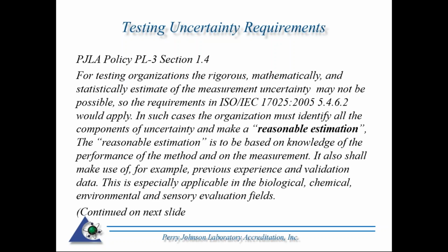In such cases, the organization must identify all the components of uncertainty and make a, and I highlighted the word, reasonable estimation. So if I'm looking at a testing lab, typically I'm looking for at least a reasonable estimation of uncertainty. The reasonable estimation is to be based on the knowledge of the performance of the method and on the measurement scope. It also shall make use of, for example, previous experience and validation data. This is especially applicable to the biological, chemical, environmental, and sensory evaluation fields.